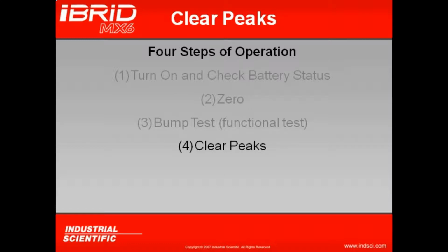Now, the reason why we write them in the code, and the reason why they do not clear if you turn off the instrument, is for accident investigation purposes. God forbid somebody goes down on a job site with one of our instruments on their side. It may be a couple days before they find the body. The battery pack will long since be dead, but the peak readings will still be there, acting kind of like a black box showing the highest concentration that person was exposed to. By clearing the peaks as our last step, we're ensuring that any peak we see is our peak and not somebody else's peak from another time.